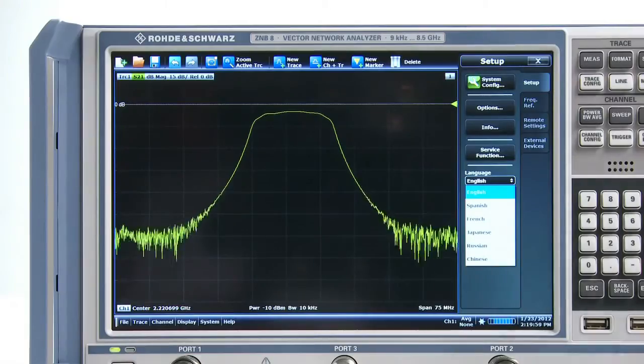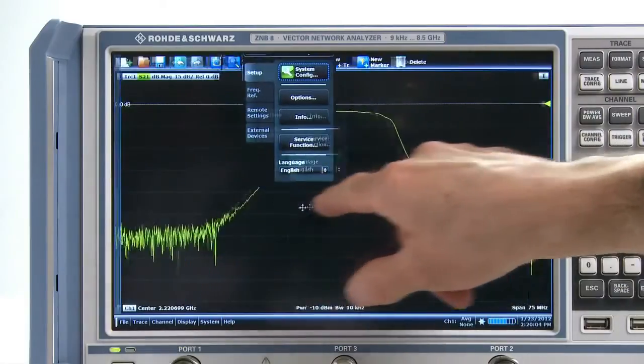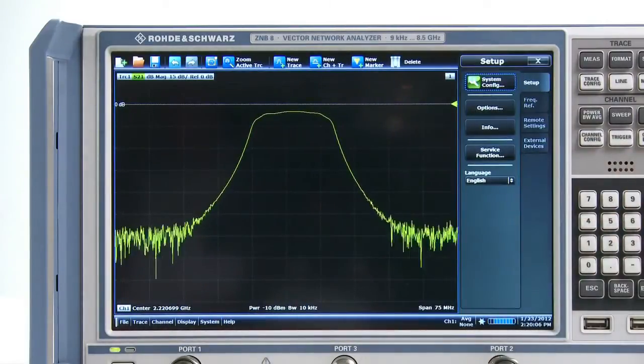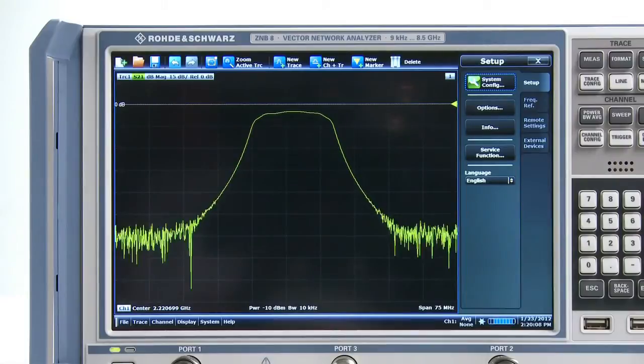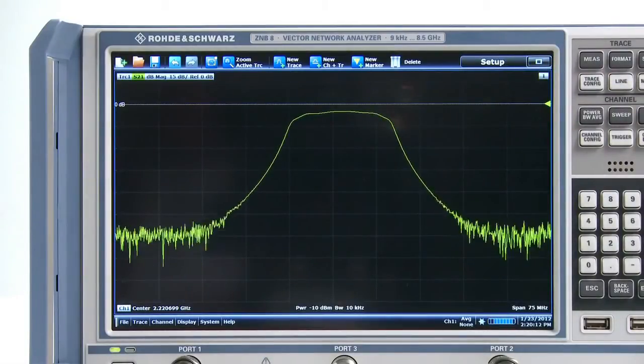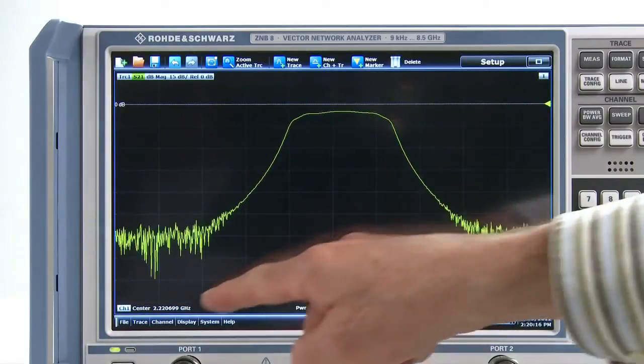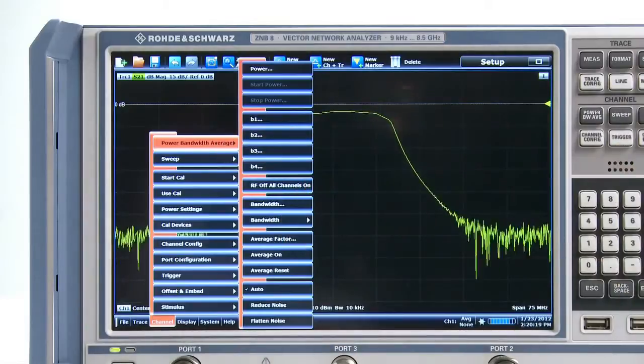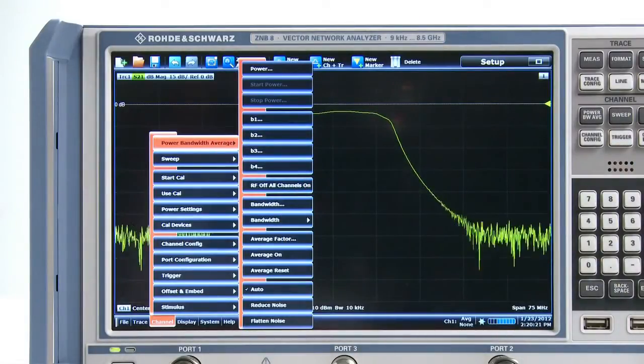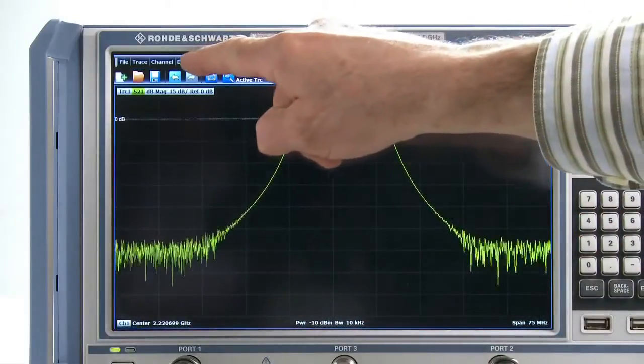Left-handers can anchor the soft panel to the left side of the screen. When configuration is completed, the soft panel can be closed so that the entire screen area is available to display measurements. If you prefer a PC-style horizontal menu bar, you can set the ZNB to show one. The bar can be anchored at the top or bottom and controlled by mouse or touch.